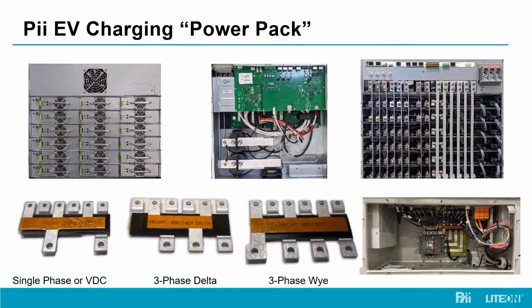With this arrangement of 3 rectifiers within a shelf, we have 3 pairs of voltage inputs to each rectifier. So we're capable of taking 240 single phase, 3-phase delta - in our case 208 or 240 delta - or 480 3-phase Y as an input to this EV charging power pack.